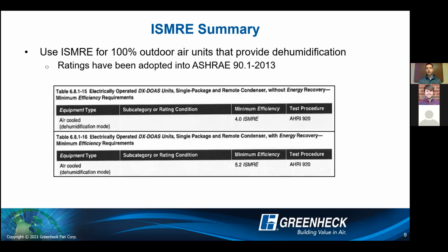So as it continues to upgrade the ASHRAE standards that you follow, you'll definitely see that requirement more and more for ISMRE. But I will say that the DOE is really trying to finalize, as we get out to that 2022, 2023 timeframe where they're hiking overall minimum efficiencies. That's when they're going to start to enforce ISMRE for DOAS equipment instead of just IEER. So while in theory you can still provide IEER for partial recirc and technically even 100% outdoor air units because the codes haven't fully adopted ISMRE, ISMRE really paints a much better picture as to what you need to test for from an efficiency standpoint. But again, if you look at the 90.1 2013 version and beyond, there will be minimum efficiencies. And also for DOAS equipment, we will put what the minimum efficiency is in 90.1 and then what our tested number is as well.